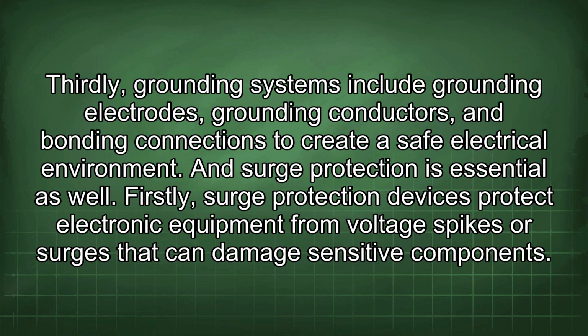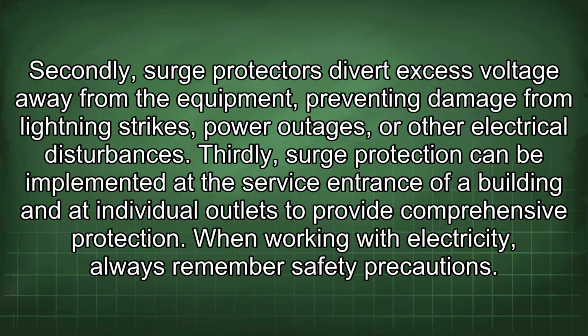And surge protection is essential as well. Firstly, surge protection devices protect electronic equipment from voltage spikes or surges that can damage sensitive components. Secondly, surge protectors divert excess voltage away from the equipment, preventing damage from lightning strikes, power outages, or other electrical disturbances. Thirdly, surge protection can be implemented at the service entrance of a building and at individual outlets to provide comprehensive protection.